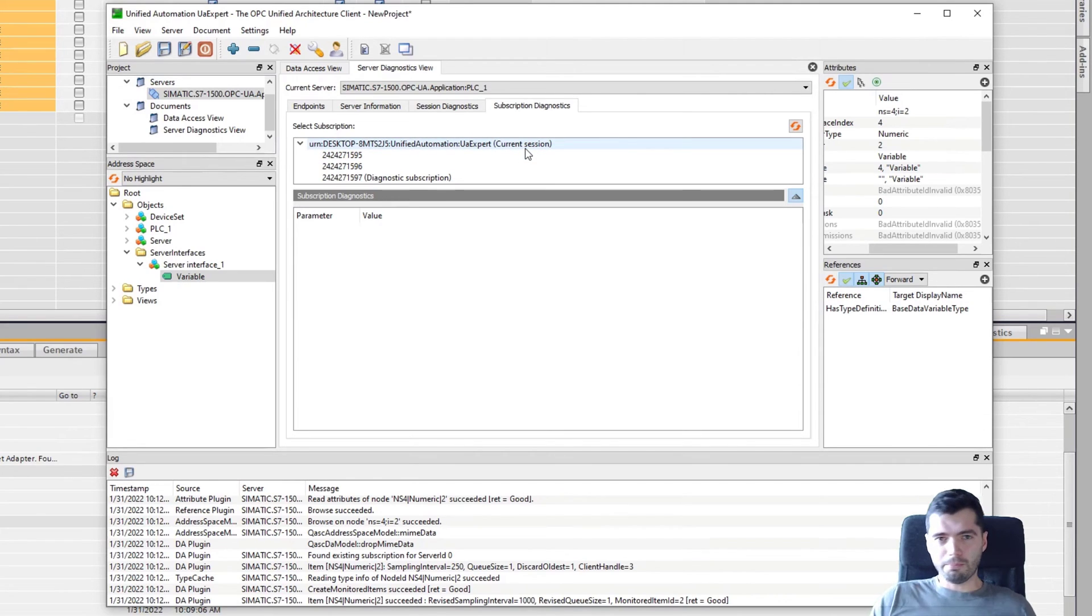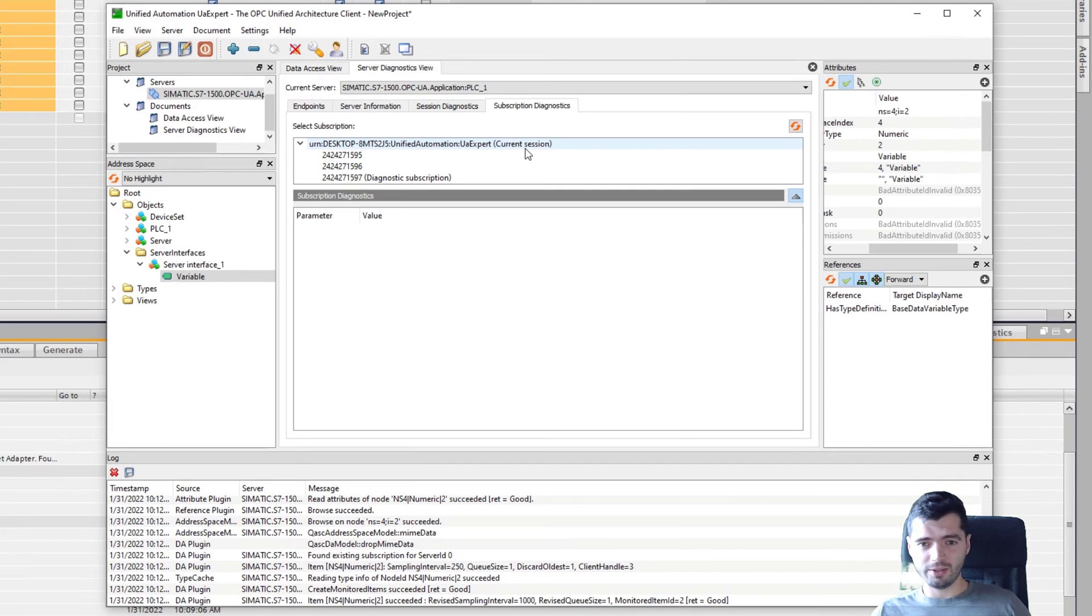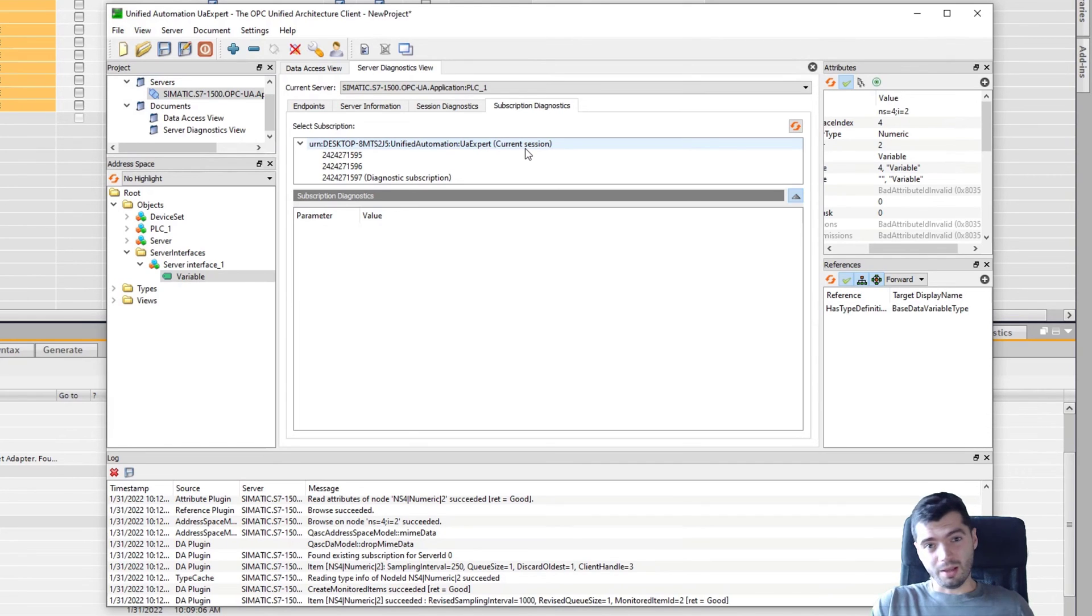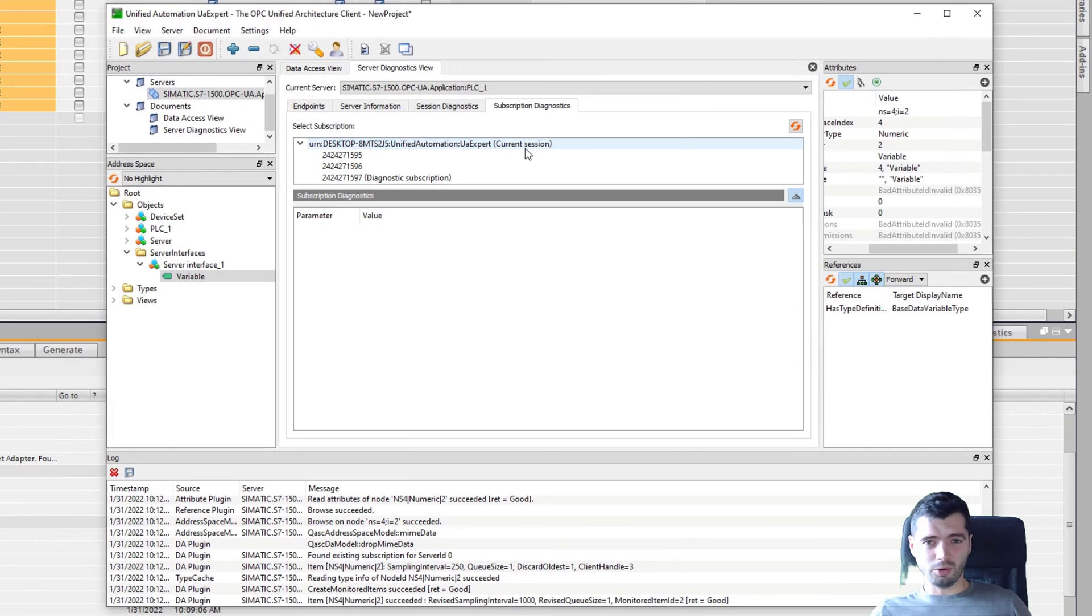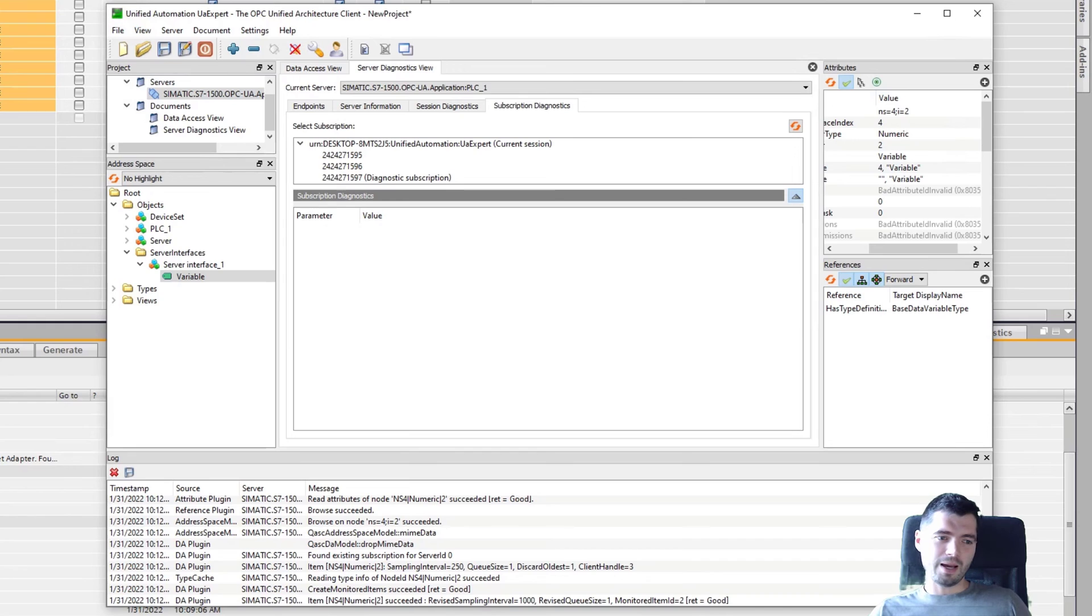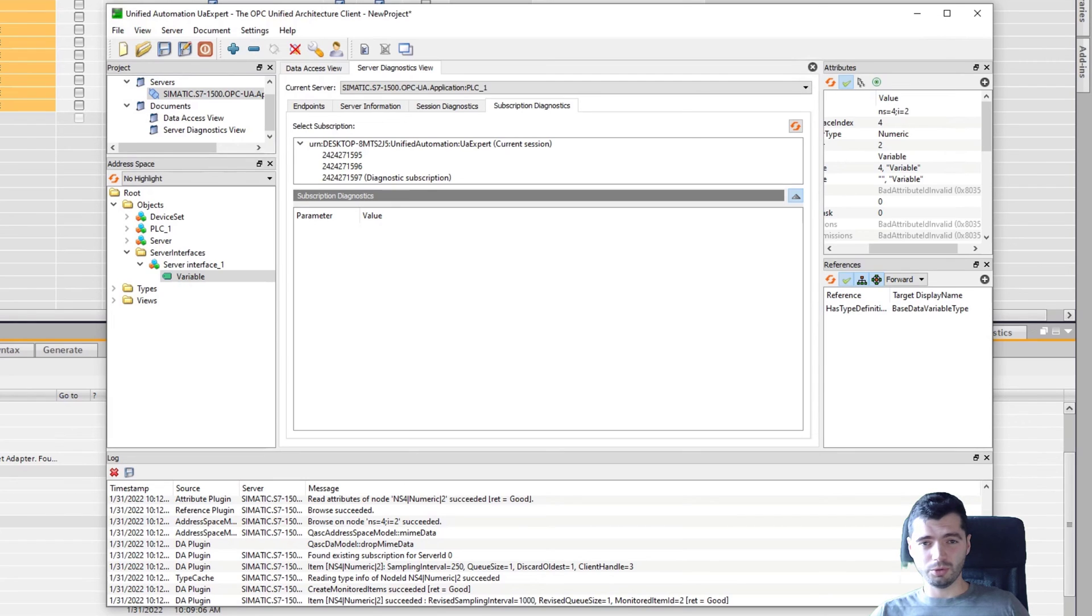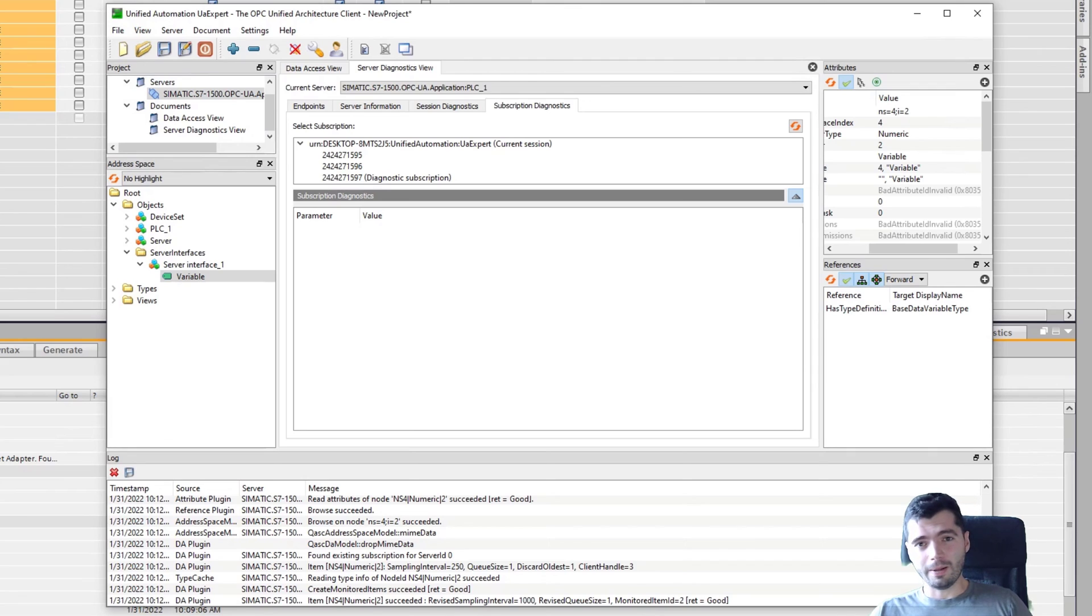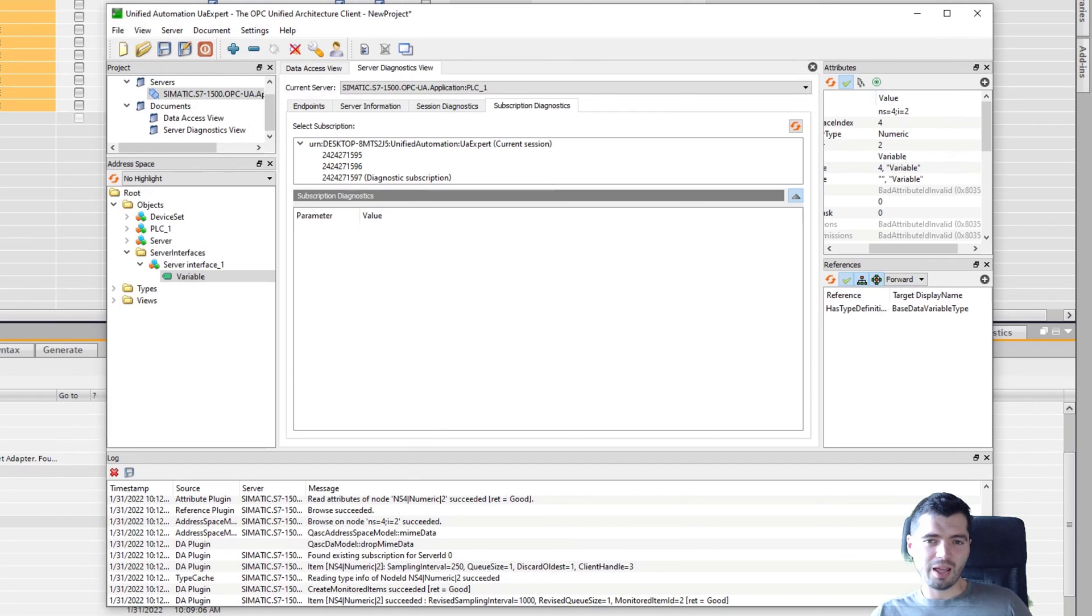You can see all the different settings here. As you can see, the minimum supported sample rate is what we had in the properties there. It tells us it's 1000 milliseconds. Then you have things around session diagnostics. You can select all the sessions that are present currently and you can see what's going on here. But again, this is more of a deep dive into diagnostics. I would say basics of diagnostics of OPC UA is doing things like, if your client can't connect, get yourself something more generic like the UA Expert, try to connect from it where your client is connecting. If you can't, then I would say try to connect directly to the PLC. If you can't connect with UA Expert directly to your PLC, this will either be down to you putting wrong details, maybe your PC having wrong configuration, or you simply not downloading the hardware config of your PLC and not enabling the OPC UA server. Now if you can connect from this place but you couldn't where you were somewhere else, then it will most likely be down to your network. And these are the diagnostics that you would need to do yourself.